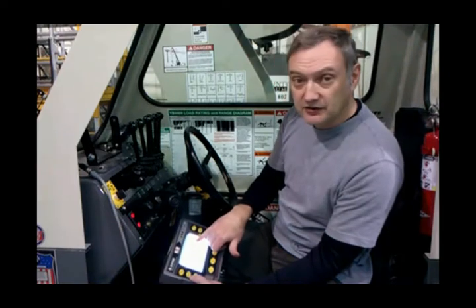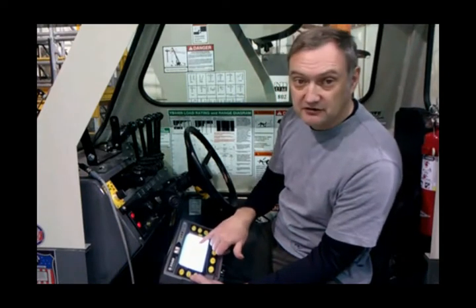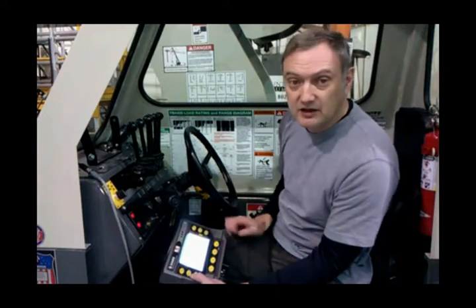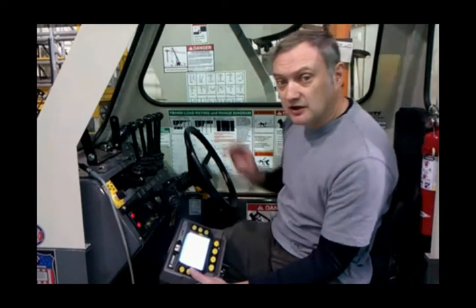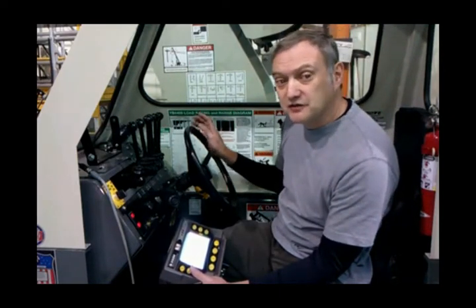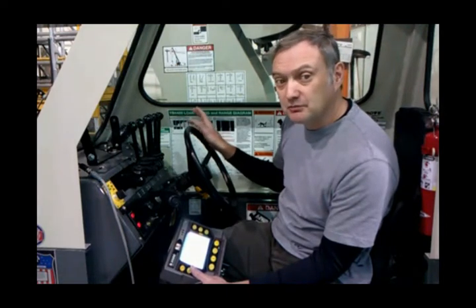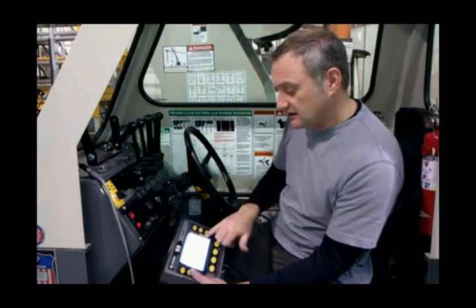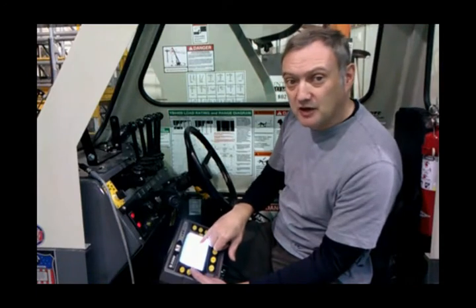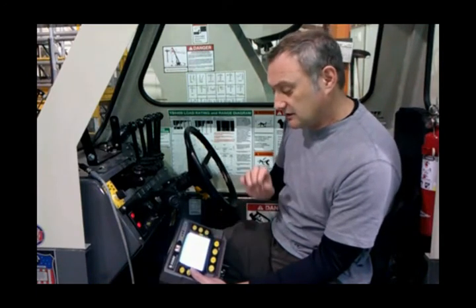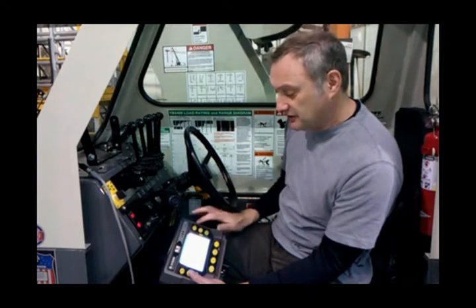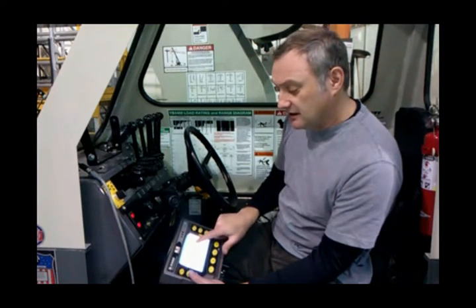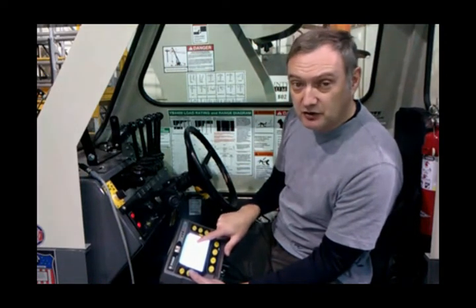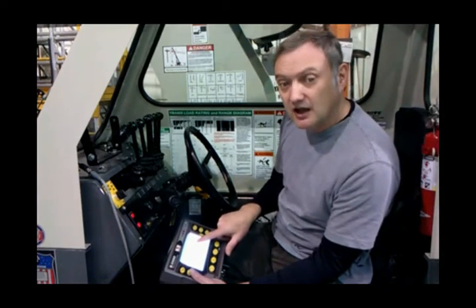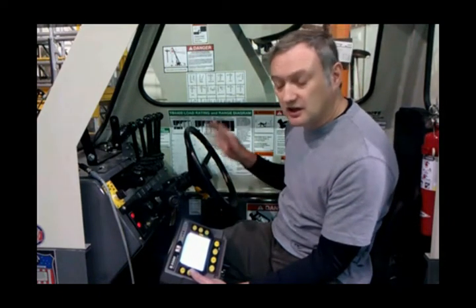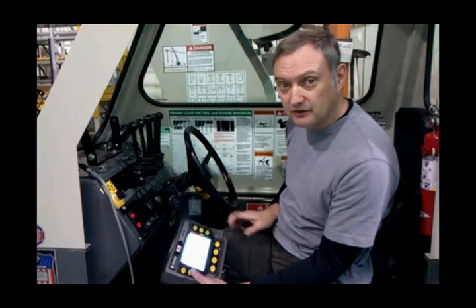The current reading is negative 2.2 with a digital value of about 305. What we're going to do now is throw the calibration switch for the bore in this pressure transducer box. Once we do that, the sensor value is going to go up over 1,000, and then we're going to hit the check mark, and the value right now that shows negative 2.2 will go to 300. I'm going to go ahead and throw the switch, and then we'll come back and we'll see what we have here.